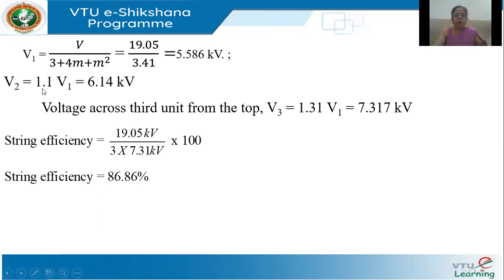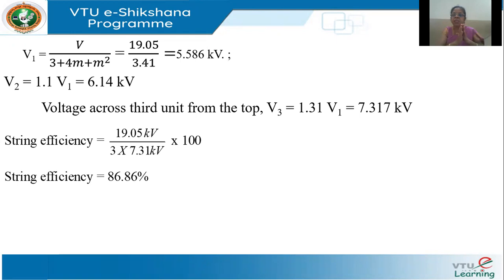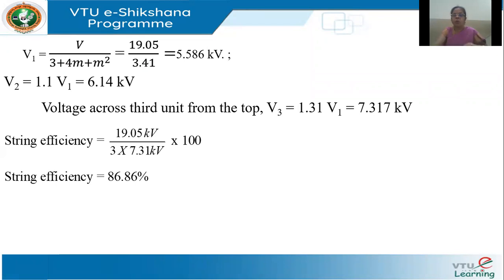Because V2 = 1.1·V1 and V3 = 1.31·V1, these ratios do not depend on the value of V. They depend only on the value of m. So if you solve the same problem for 66 kV or 220 kV with m = 0.1, V1, V2, V3 values will be different but the string efficiency will still be 86.86%. The string efficiency does not depend on the voltage level.